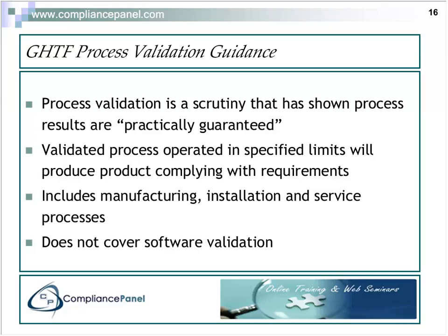Validated processes are operated in specified limits, and if we operate within those specified limits, it is going to produce product that complies with the requirements. It does include manufacturing, and of course we said service processes, but notice the word installation here has now been brought up during the Global Harmonization Task Force.